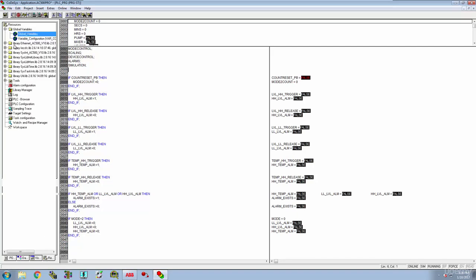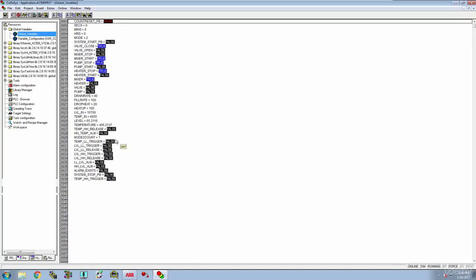For right now I'm more interested in actual system operation and seeing what's going on. Our mixer is running, we're in mode 3. Right now I see we've got our pump off and our levels in good shape — it's coming down. Pretty soon we should see our pump go on once we get down to around 20 or 30. Our mixer is on because our temperature is at 350.